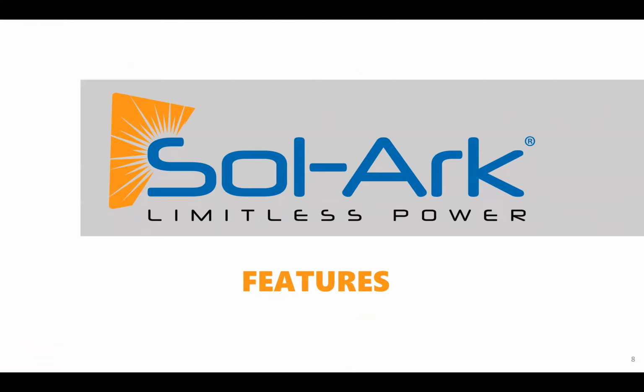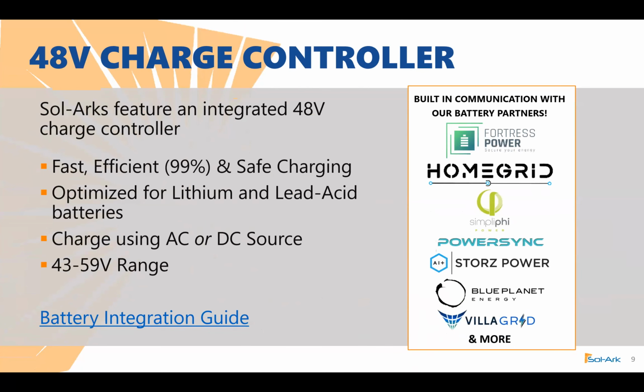Now let's go across a couple of features of our product. First of all, we have a 48 volt charge controller inside our Sol-Arks. Again, it's fast, efficient, up to 99% for safe charging. We're optimized for lithium and lead acid batteries, and we can charge that battery not only from a DC source or the PV connected to the inverter, but we can also charge from external AC sources as well. That means we can charge from a grid, we can charge from a backup generator, or we can charge from an AC coupled source. Our voltage range on the battery terminal can go down as low as 43 volts before it disconnects and charge up to 59 volts. We can even charge higher than that with appropriate temperature compensation programmed in the inverter, up to 63 volts.